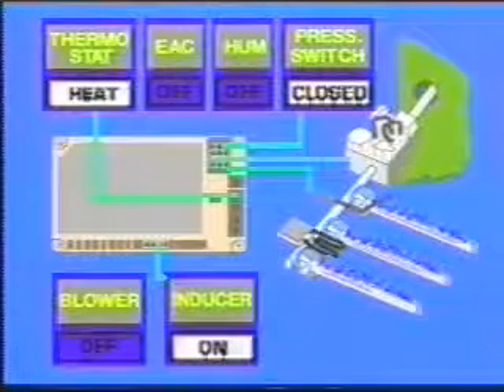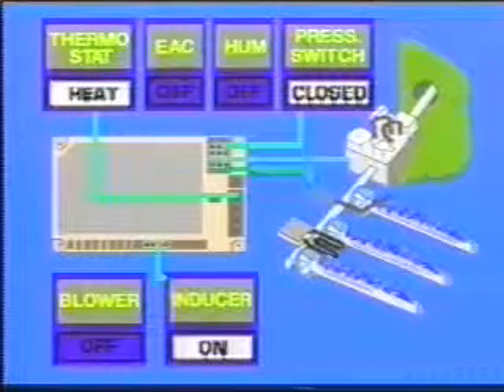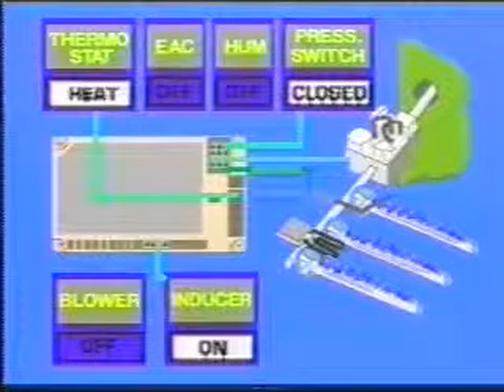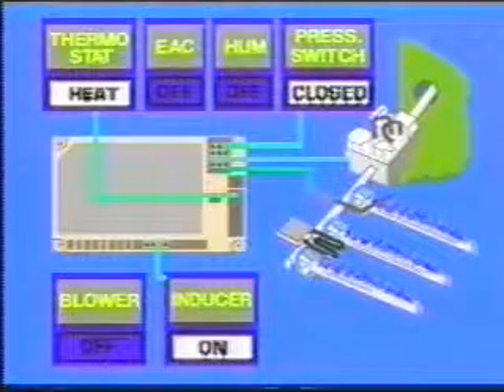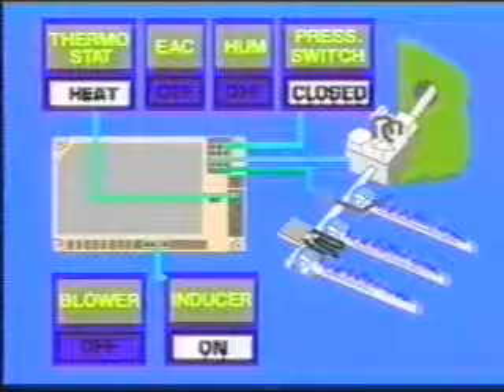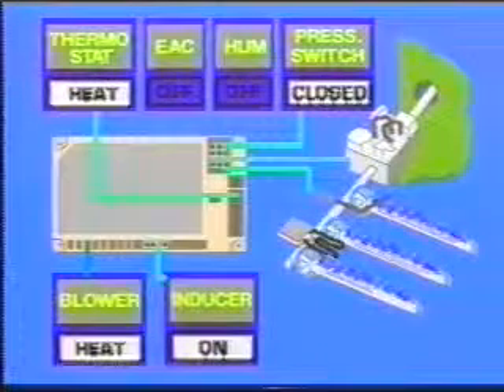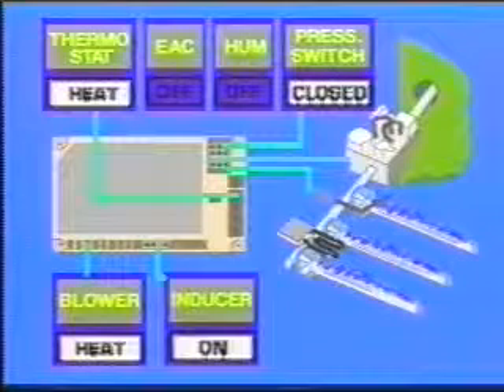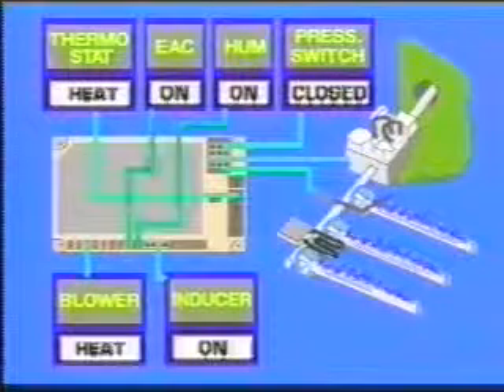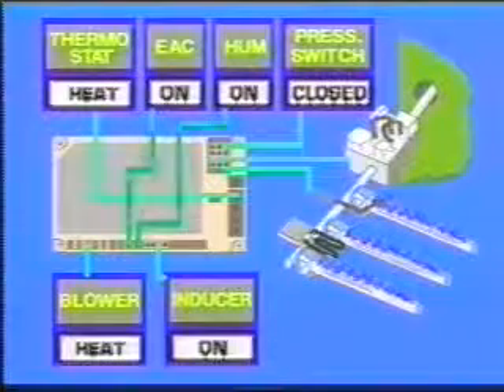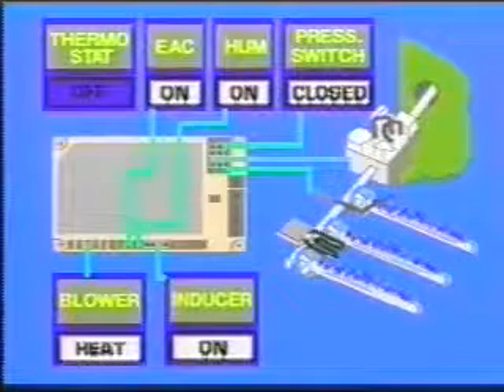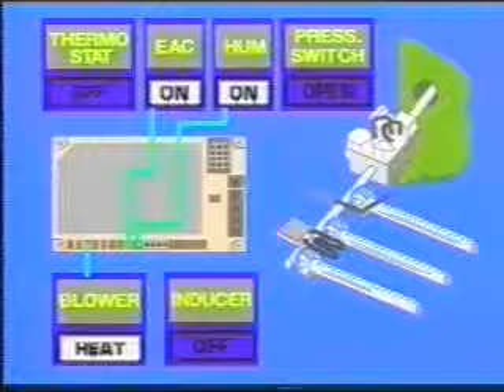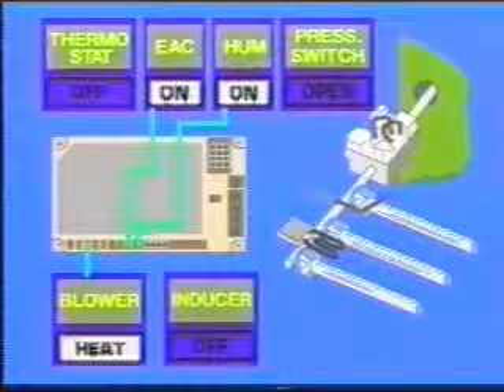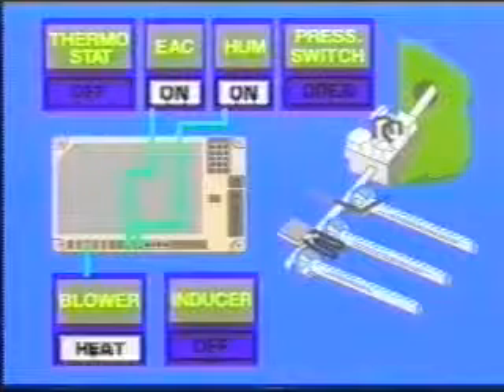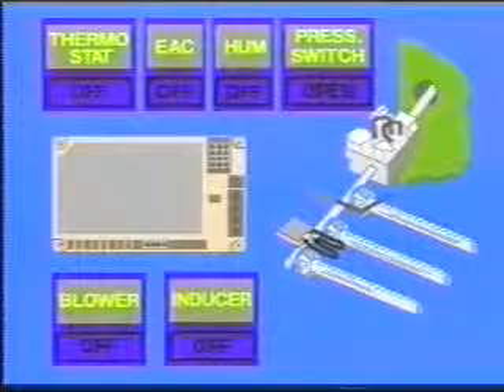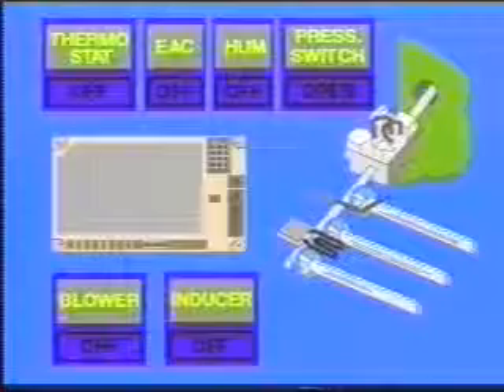For two-stage systems, the inducer fan may go to higher speed, and the second stage of the gas valve may be energized. After the delay to fan on period ends, the blower is energized at heating speed. The optional air cleaner or humidifier circuits are also energized at this stage. When the thermostat is satisfied, the gas valve is de-energized and the delay to fan off period begins. After the delay to fan off period ends, the blower, humidifier, and air cleaner circuits are de-energized.